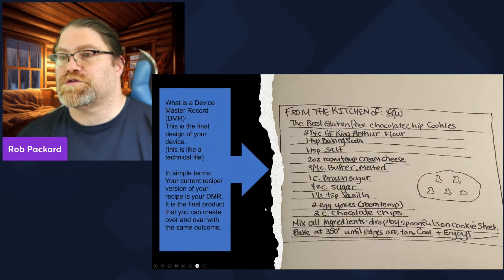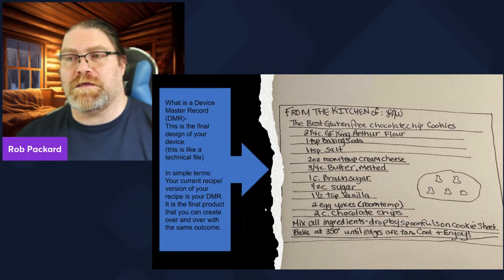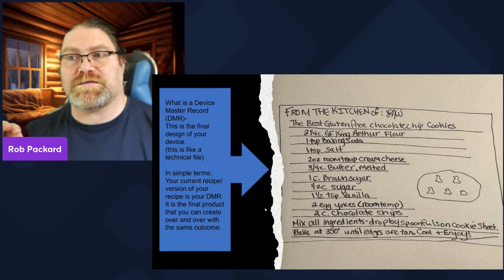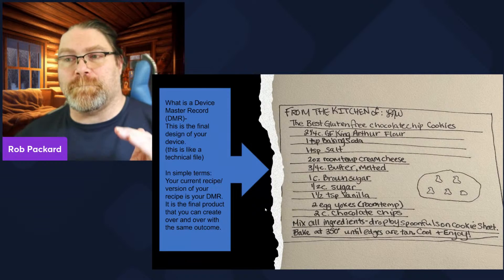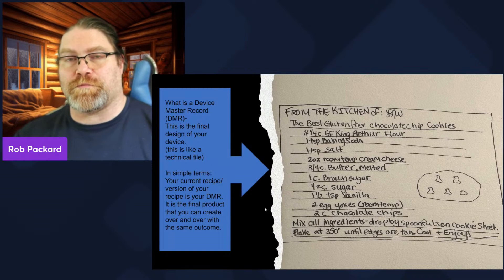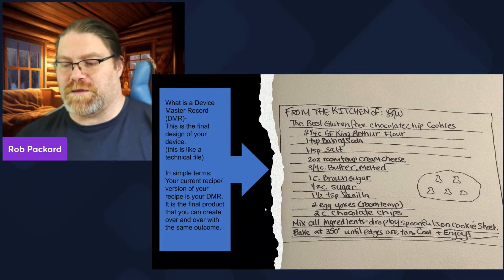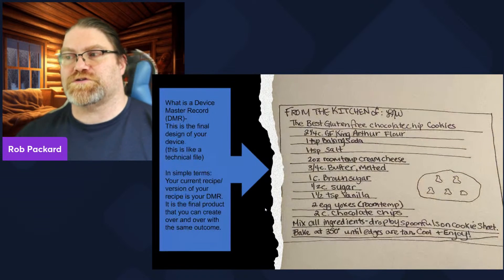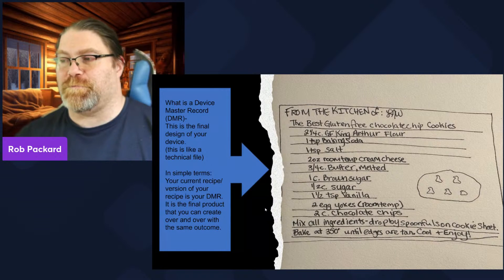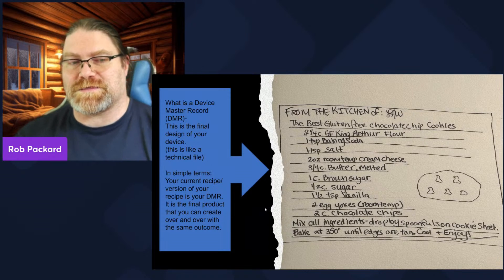Next is the DMR — a device master record. Not a design history record, not a design master record — it's a device master record. This is how to make the device. This is your recipe. So this is Lindsay's final version of her best gluten-free chocolate chip cookies. This is the best one — it has a name. This is the current recipe: how we make it the same way every single time.